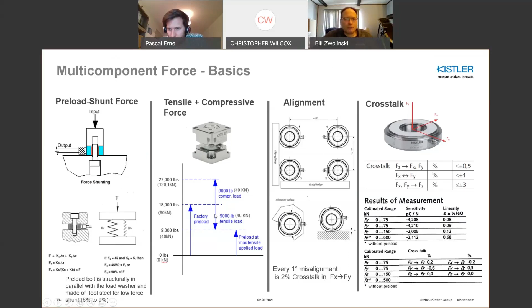So it's one of these things that's practical and easy to do when you have a straight edge on the force sensor. And obviously crosstalk always comes into play regardless of what sensor you're using. The calibration certificate gives the exact crosstalk of a sensor, and it's the best way to see the performance of your sensor in terms of your particular application. In terms of preloading, you have to ensure that the sensor itself doesn't rotate. So there are a couple of different methods here. We talk about the cylindrical pin method, where you put 2 cylindrical pins near the connector, and as you preload the top plate to the bottom plate and through the force sensor, the sensor will not rotate because it's constrained at the connector.